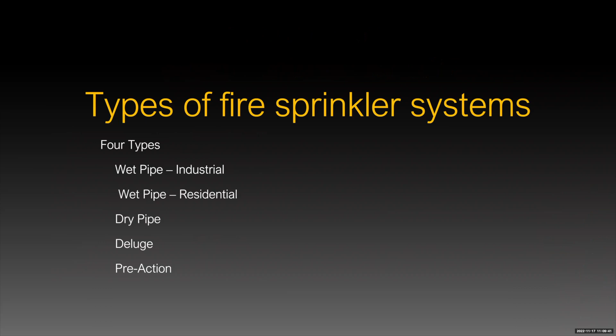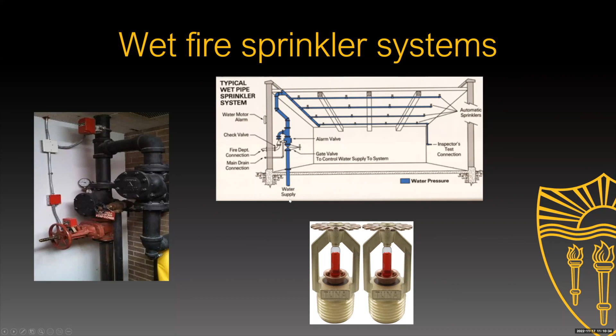So if you look at, I'll say, an industrial wet fire system, you typically are going to see a situation where water comes in from the main, from the supply, goes into the fire system, and then from there it goes directly into the sprinkler heads. Simple as that. Okay. And you can see that the sprinkler heads, here's an example, they do have a little heat element right here. So you can see there's a little glass bulb with a liquid inside, so that if there is a fire and the liquid gets heated up, the bulb breaks and the water starts coming out. Okay. So it's a pretty simple concept. The whole idea of this wet system is the fact that it is fully charged with water. So the whole system is fully charged with water, and the water is coming from the water supply. Okay.